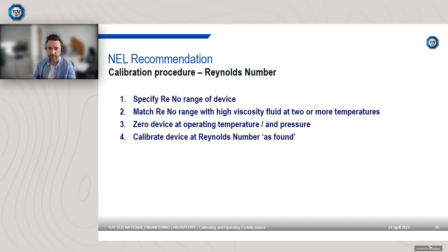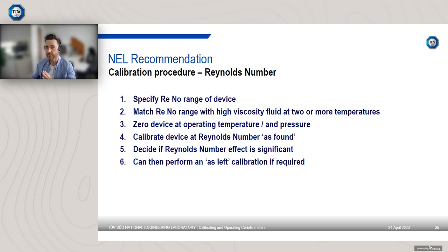We don't always do it. I'll discuss that in a minute, because I can see you've got a question on that. We then calibrate the device at the Reynolds number as found. We decide if the Reynolds number effect is significant. It isn't always. We find for certain devices there's a significant Reynolds number effect. For other devices, depending on their aspect ratio, the Reynolds number effect can be lower. It might still be within that 0.1%.